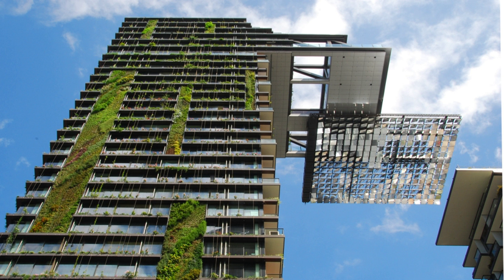Air source heat pumps are inexpensive relative to other heat pump systems. However, the efficiency of air source heat pumps declines when the outdoor temperature is very cold or very hot, therefore, they are only really applicable in temperate climates. For areas not located in temperate climates, ground source or geothermal heat pumps provide an efficient alternative. The difference between the two heat pumps is that the ground source has one of its heat exchangers placed underground, usually in a horizontal or vertical arrangement.